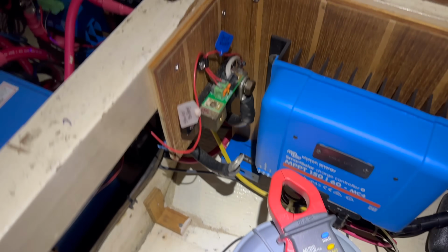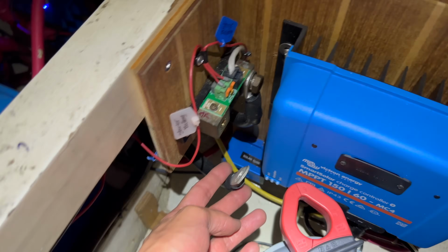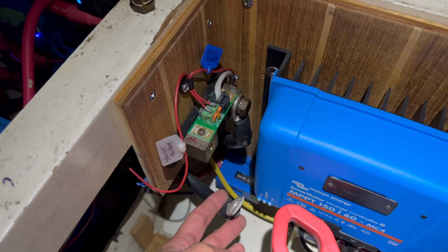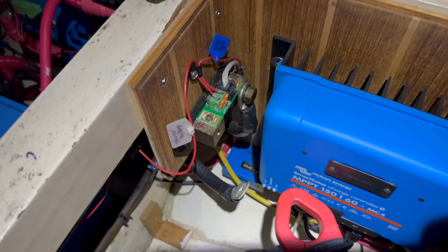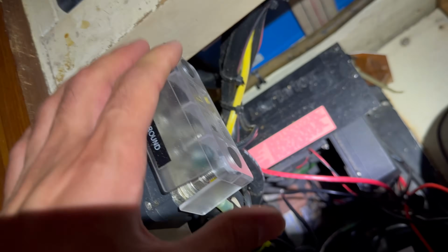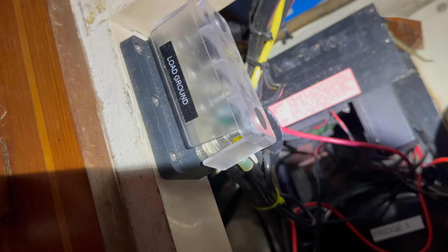Okay, so you can see here, per those instructions, I've disconnected the system side of the shunt, and it's still reading 2.77 amps. Let's follow here — that's this one right here. All the negatives for the whole battery system collect right here at this load ground.